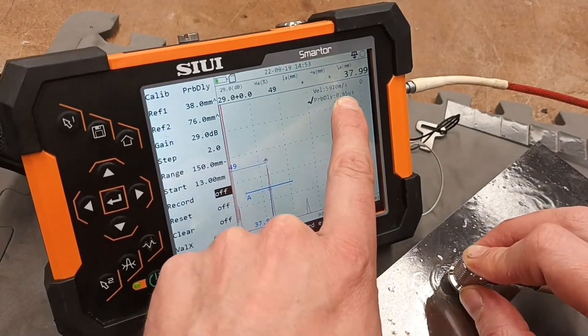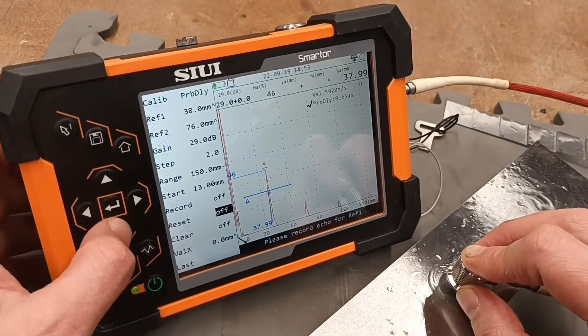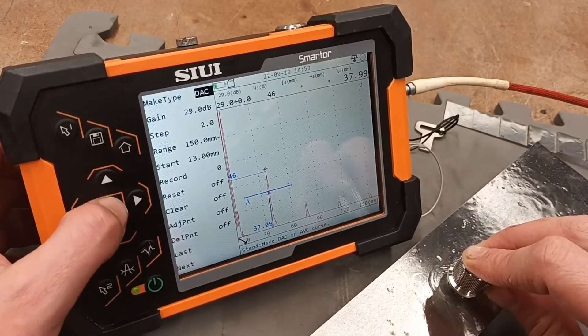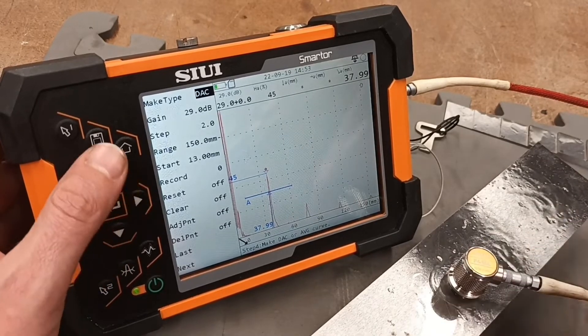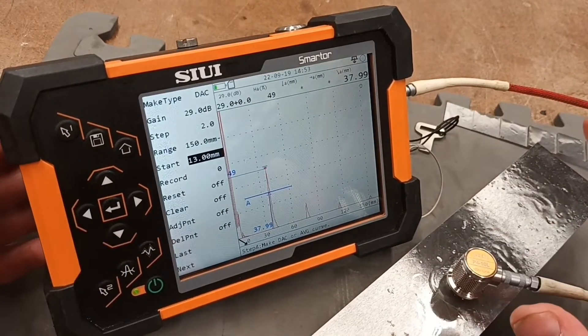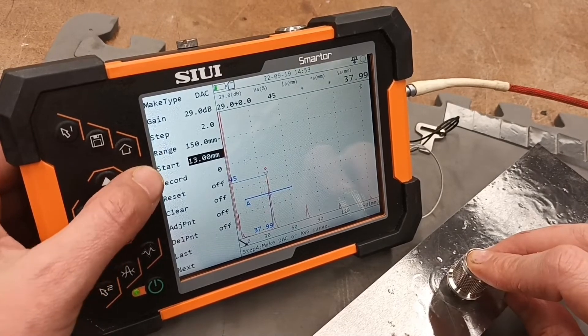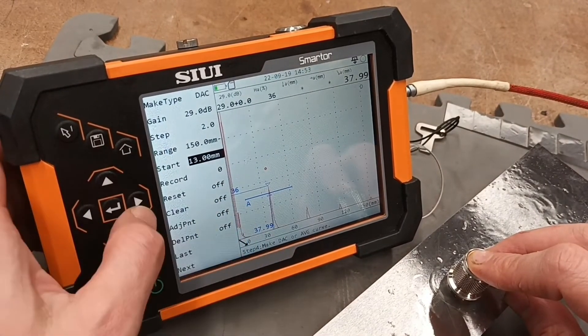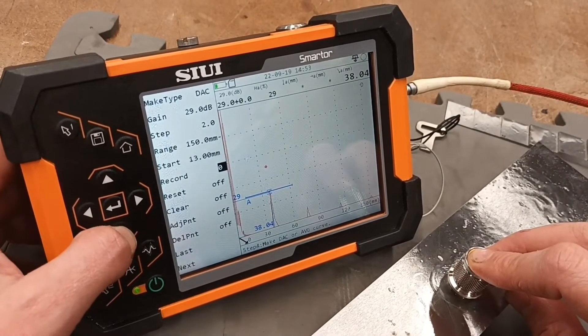It's given us the velocity and our probe delay. From here we can either reset it to clear the information or input some more data. That's done, so we'll just continue — next. We're going to be asked to make a DAC curve now. Just following the simple on-screen information, it's setting the range to 150, starting the gate at 13 millimeters, and it's making the DAC or AVG curves. We'll start with the DAC.